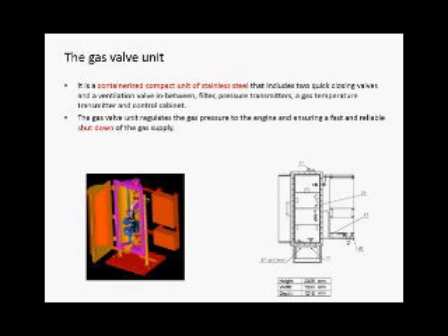This is how the gas valve unit looks. It is a containerized compact unit of stainless steel, including quick-closing valves, a ventilation valve, filter, pressure transmitters, gas temperature transmitter, and control panel. It regulates the pressure to the engine and ensures fast, reliable shutdown of the gas supply if required. This control issue is also a huge design issue in the case of conversion.